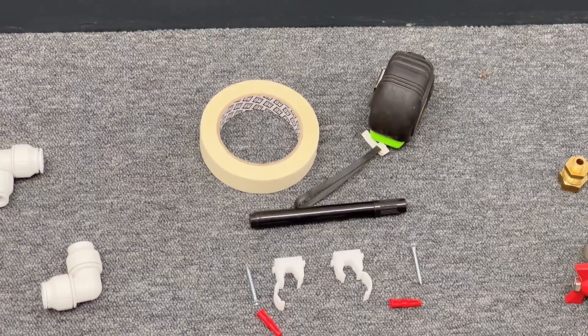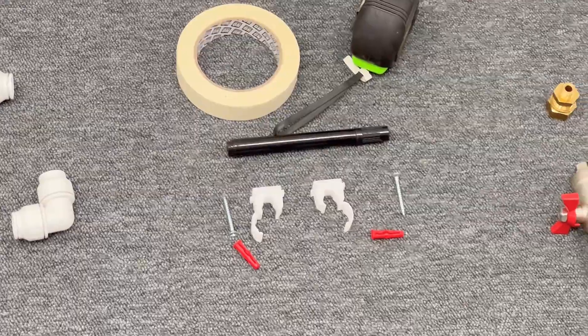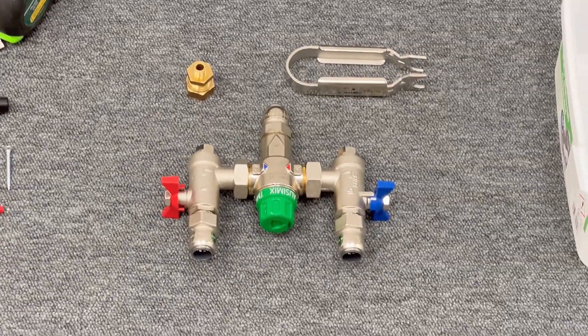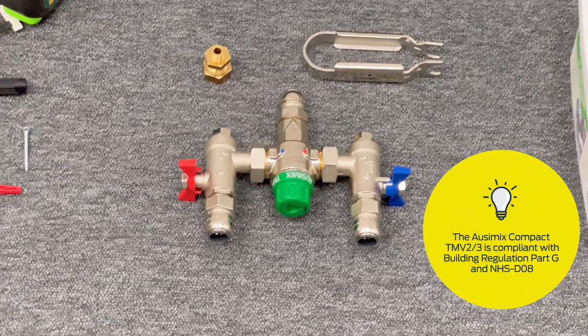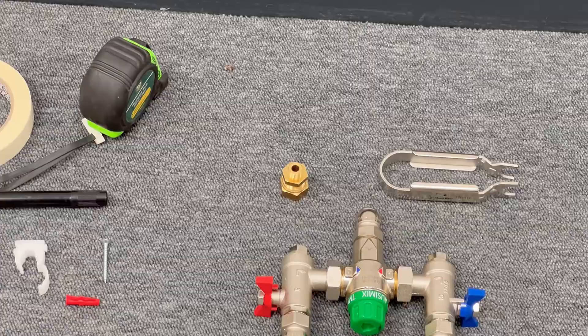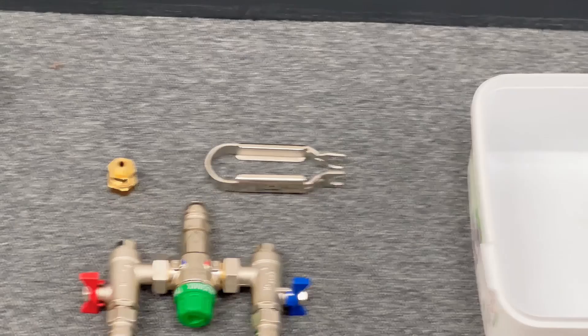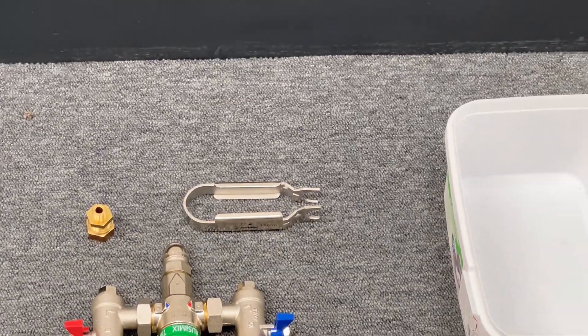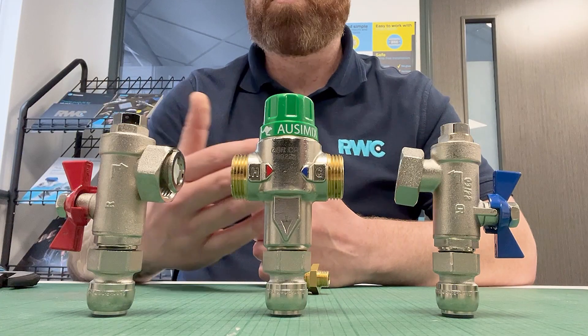Masking tape, a tape measure, a pen, two pipe clips and 6mm screws and rawl plugs. Due to the nature of the application being TMV3, I've opted for the Ausimix TMV2/TMV3 thermostatic mixing valve. This is the SharkBite version with push fit connections. I've also opted for the potable adapter that allows me to run my cold pipe directly from the cold adapter on the valve up to my cold tap. I've also got my 15mm disconnect tongs and a tub for when I drain down.